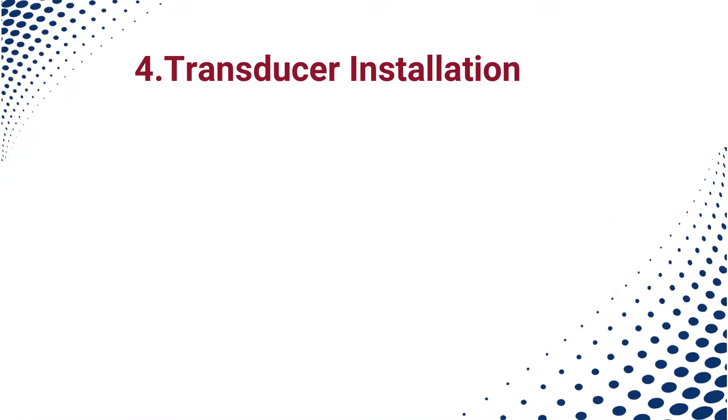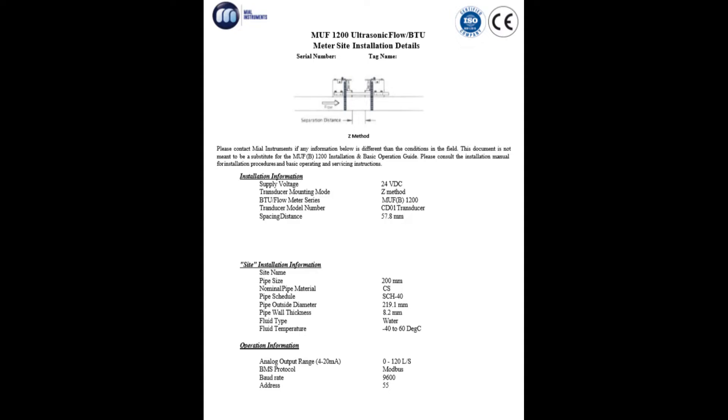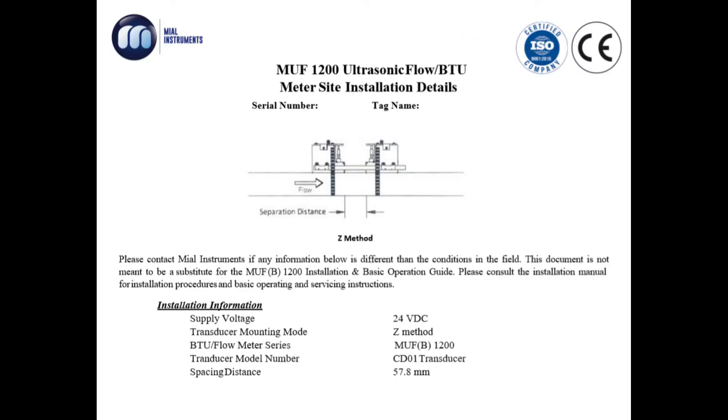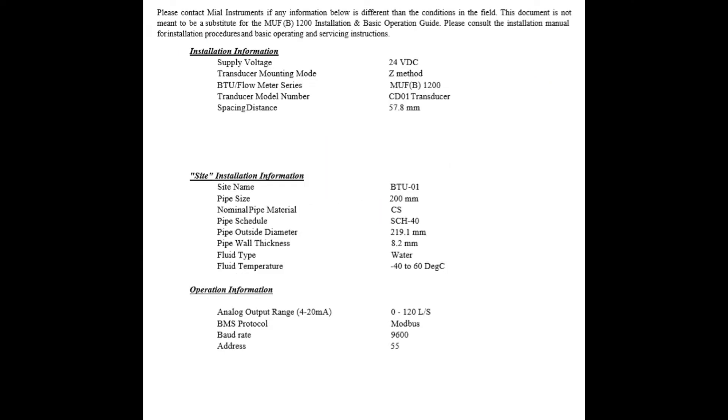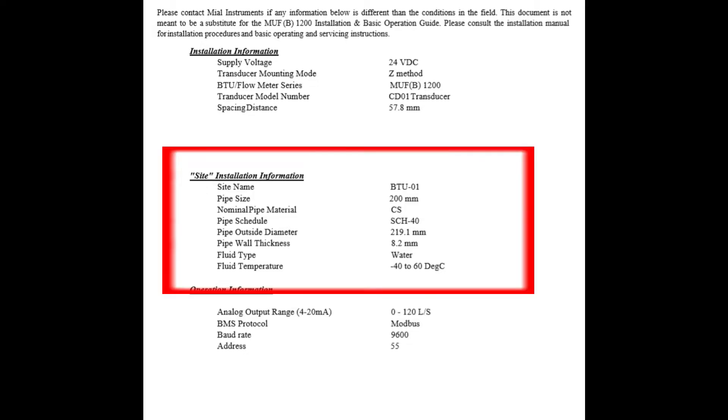In this section, we demonstrate how to install using the Z method. Before doing installation, refer to the site installation data sheet for configuration and installation details. Check and confirm the actual pipe size in the site and the programmed and calibrated pipe size in the meter are the same. If there are any changes, please contact us for further technical support.